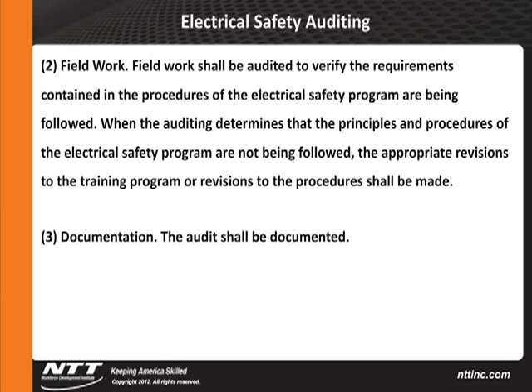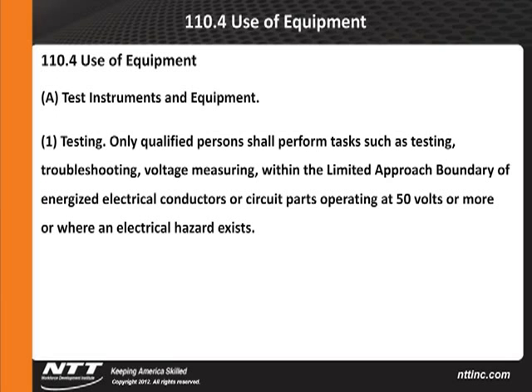Use of equipment, testing and instruments. Testing. Only qualified persons shall perform tasks such as testing, troubleshooting, voltage measuring within the limited approach boundary of energized electrical conductors or circuit parts operating at 50 volts or more where electrical hazard exists. Again, right now I go into facilities and I ask people, what are you folks doing? I got an operator, I do a voltage check, I do this. The standard says that individual has to be a qualified person for the task they're performing with the appropriate PPE.